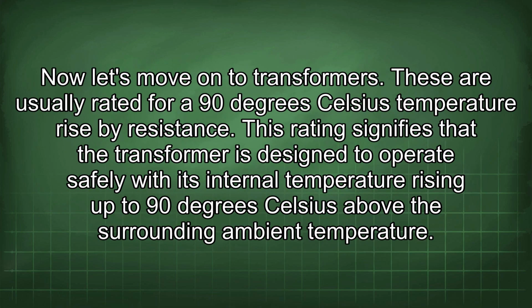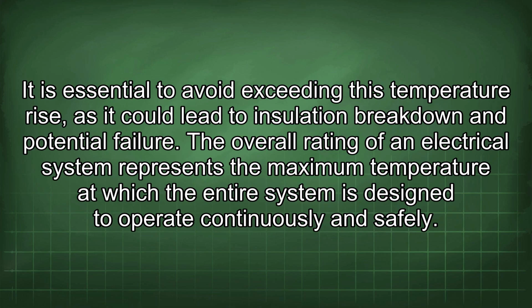Now let's move on to transformers. These are usually rated for a 90 degrees Celsius temperature rise by resistance. This rating signifies that the transformer is designed to operate safely with its internal temperature rising up to 90 degrees Celsius above the surrounding ambient temperature. It is essential to avoid exceeding this temperature rise, as it could lead to insulation breakdown and potential failure.